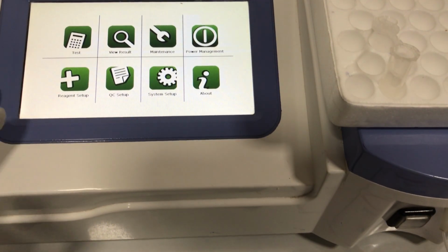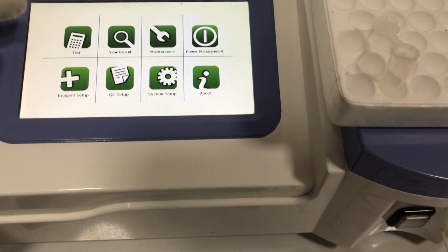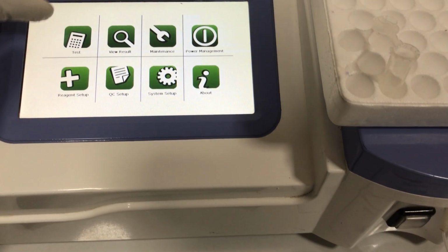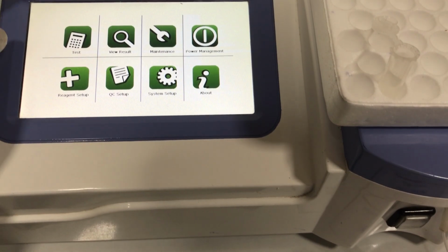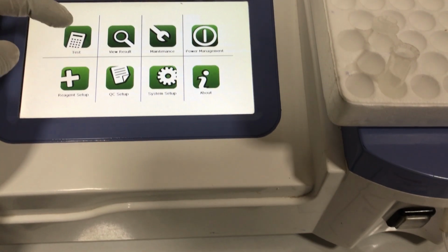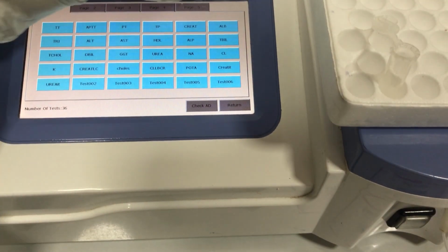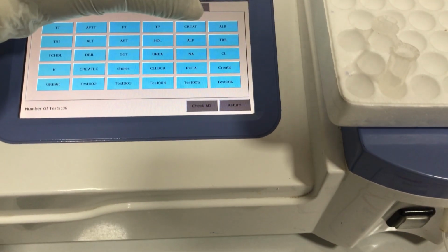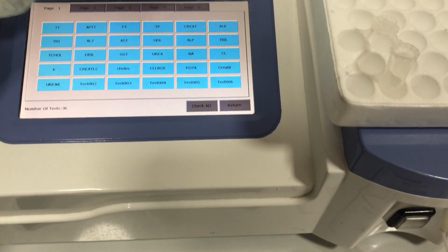Okay, so this is a semi-auto analyzer, and we are going to use this. I'm going to show you how we do it. So this is the test button, then results, maintenance, power management, reagent setup. We are mainly going to use these two, the test and then the reagent setup. Okay, so I go to my test site, and then this is where I've programmed creatinine. That's the creatinine.